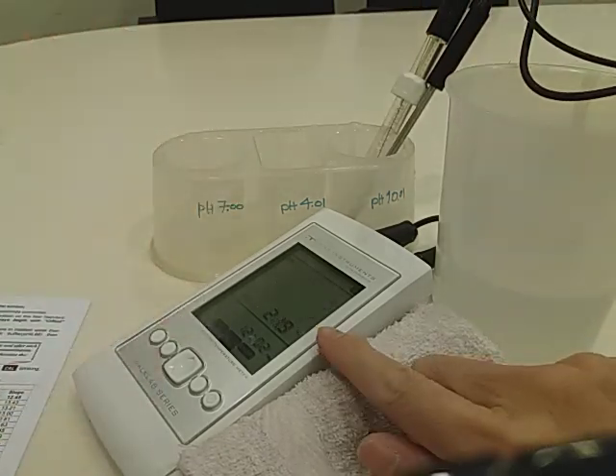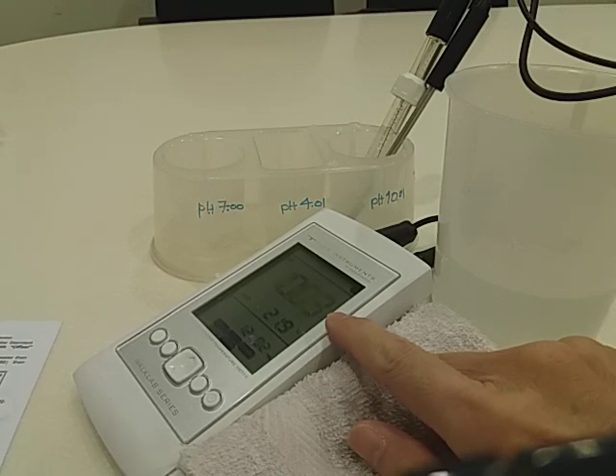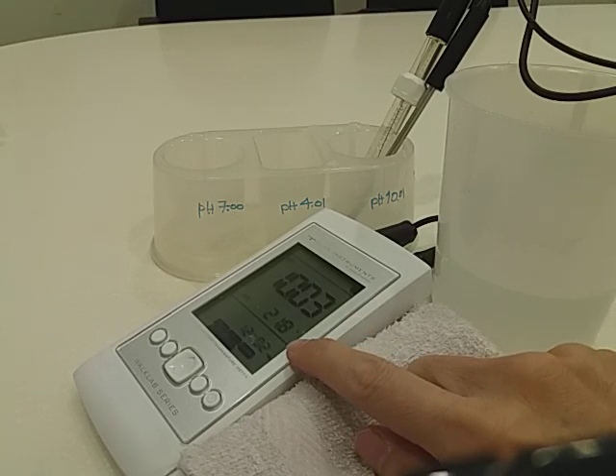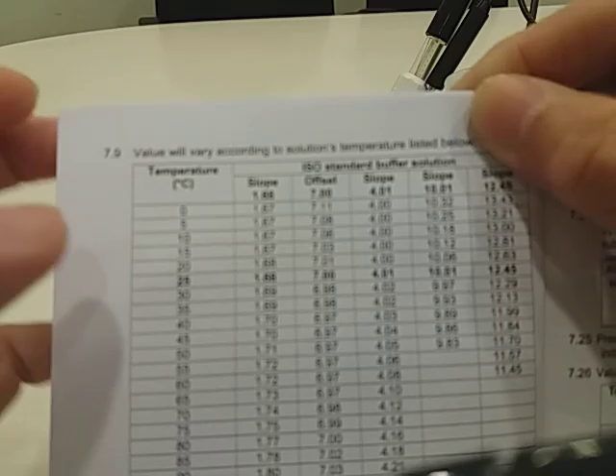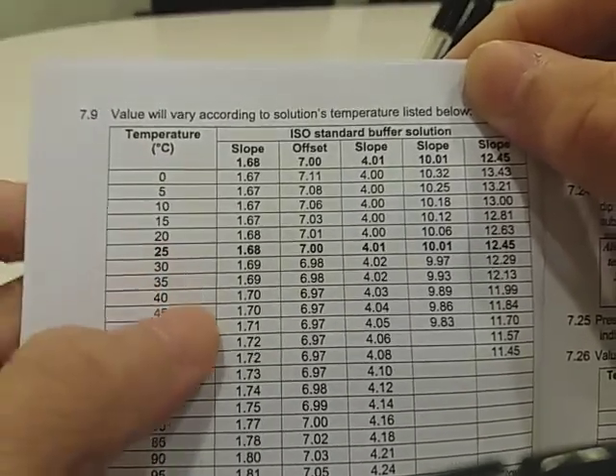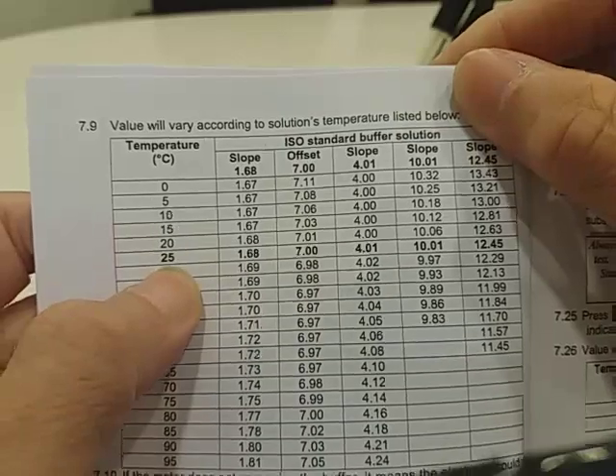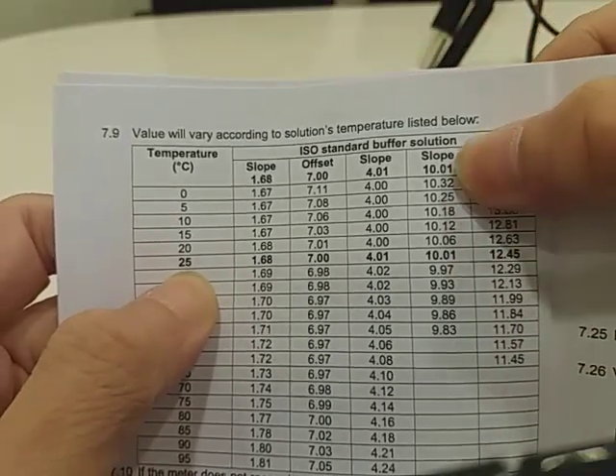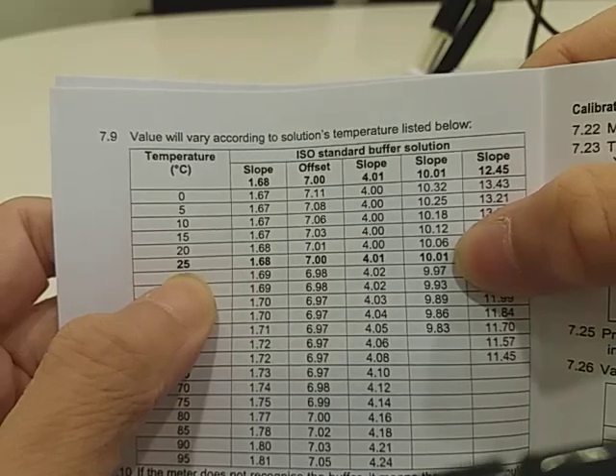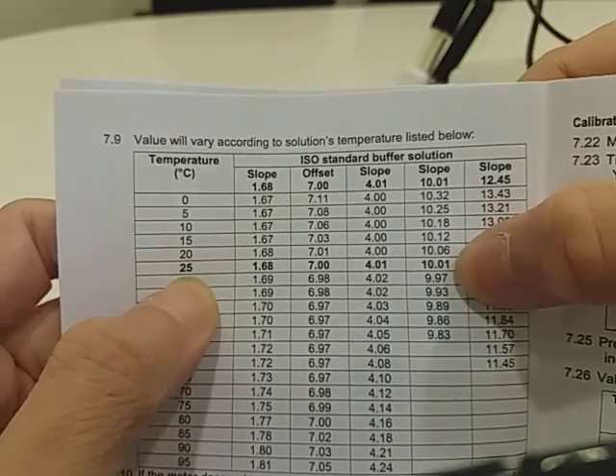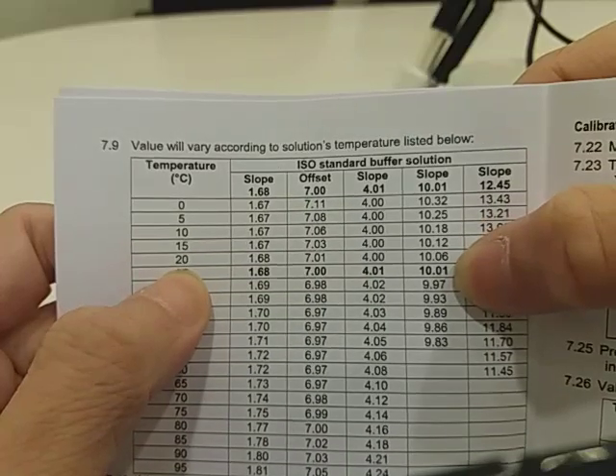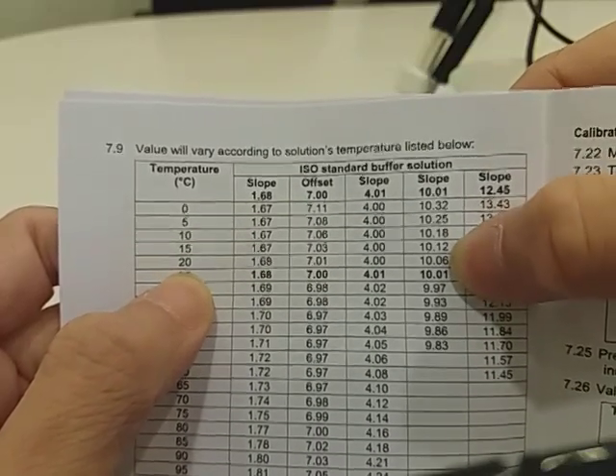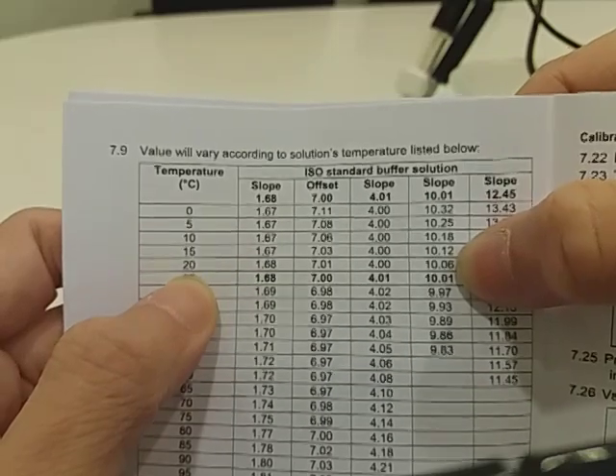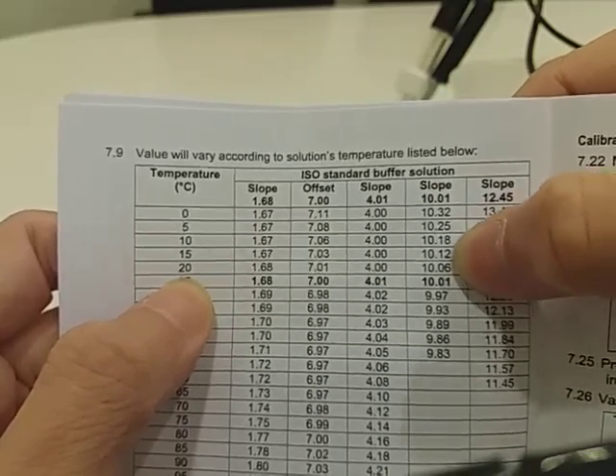Now you can see that the reading is 10.03 at 21.8 degrees. Again, we look at the manual. So 22 to 25 degrees, you can see the pH 10 reading is 10.06 to 10.01. And our reading is about 22 degrees, which is between these two readings, which is around 10.03 or 10.04, around the region. Let's get back here.